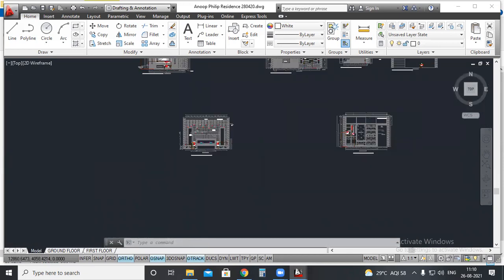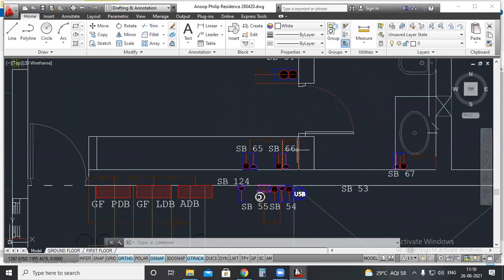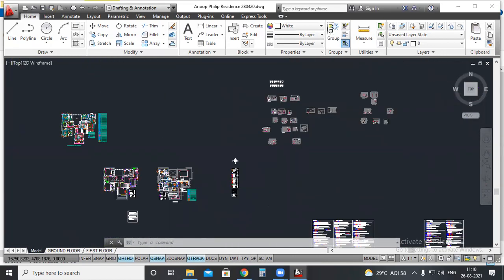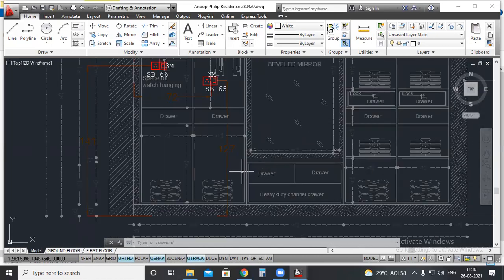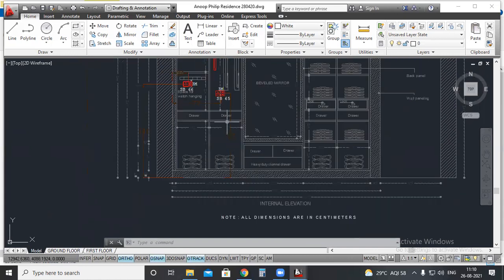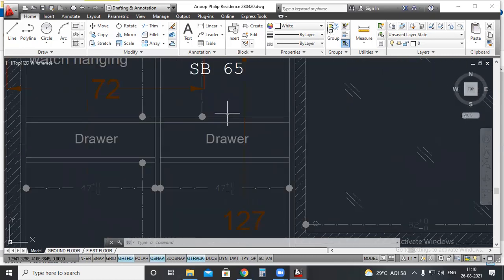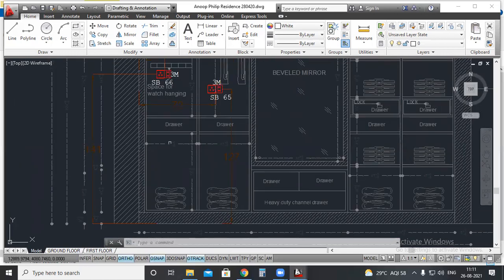This is coming inside the cupboard. This one has an input from the client. The client told us he needs 2 sockets inside the wardrobe area. That was his idea. You can see here 2 sockets at different heights. We have specified the height from the floor. You might think you can provide the height from this particular drawer, but no, because at the initial stage there will be no drawers or cabinets. So you have to specify the height from the floor and from the nearest wall.